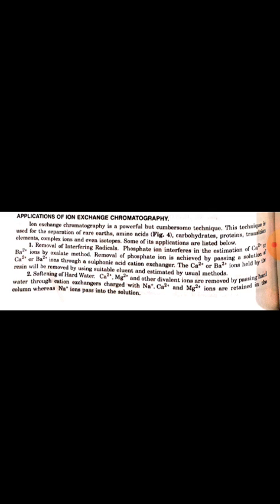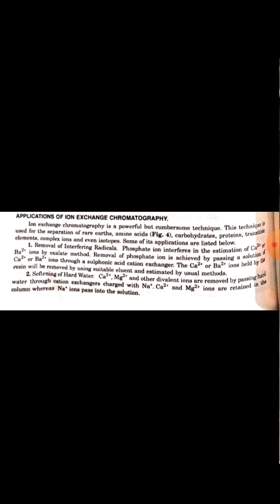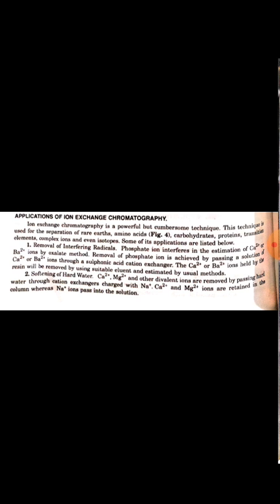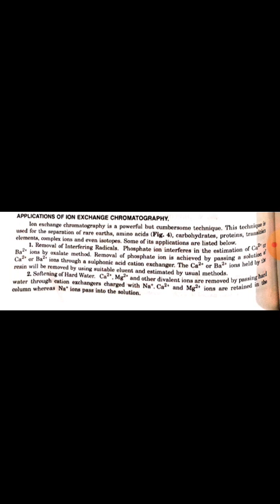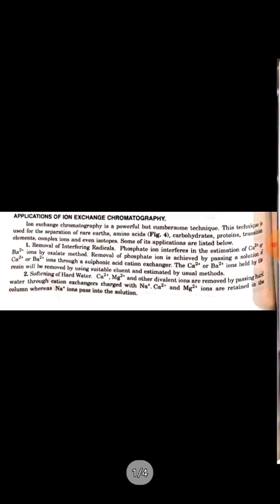Second is softening of hard water. Calcium and magnesium and other divalent ions are removed by passing hard water through cation exchangers charged with sodium ions. Calcium and magnesium ions are retained in the column whereas sodium ions pass into the solution.